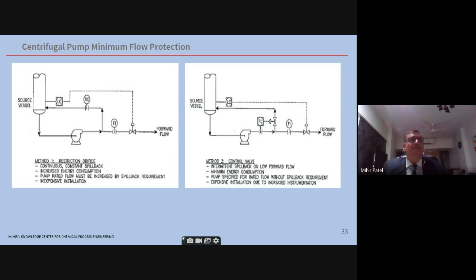Please remember this. On the right-hand side is another way of doing it, through a control valve. This control valve is normally closed. It will open only when the flow senses, let's say 5 meter cube is there and 1 meter cube is the minimum flow, that the flow goes below 1 meter cube, and it will ensure that 1 meter cube is always there on the pump, above the minimum flow.